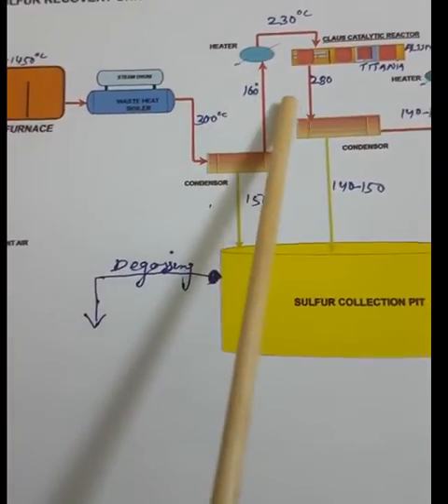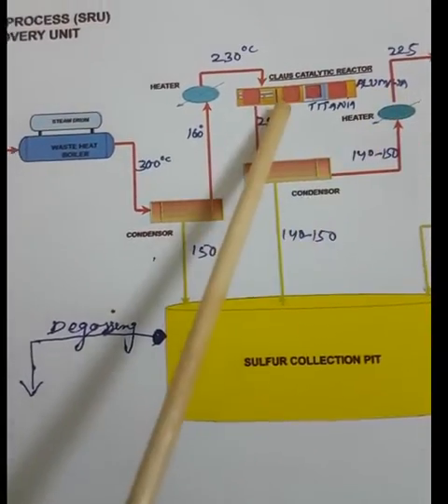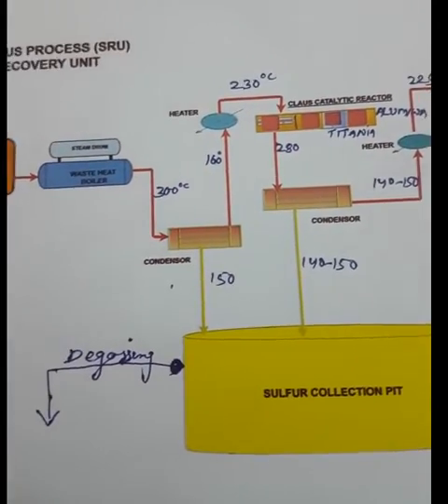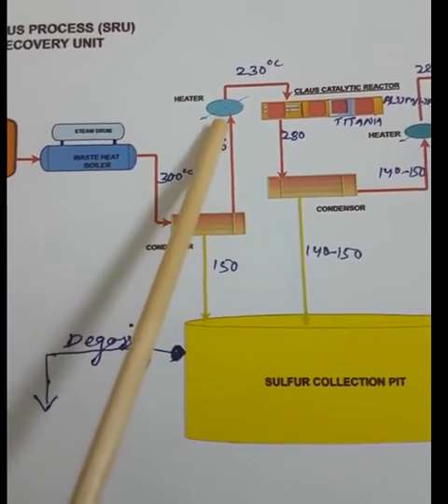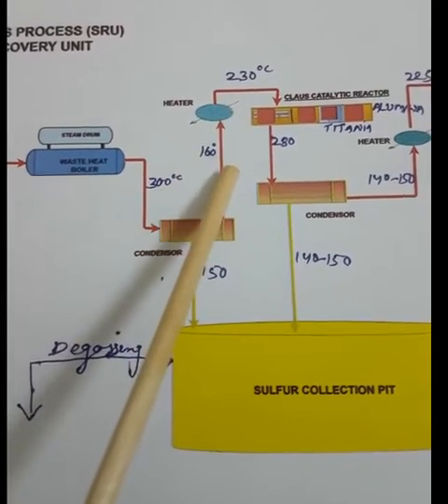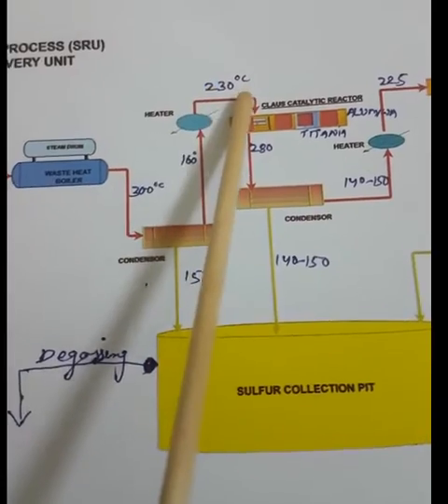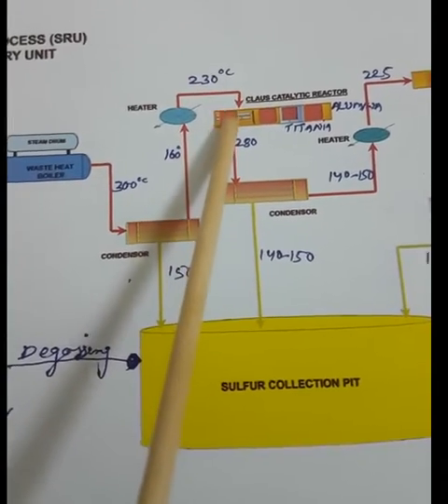In the Claus reactor, the catalyst is alumina and titania. If we send the gas at 160°C directly, there would be sulfur plugging of the catalyst bed. So we preheat the process gas to 230°C in the preheater, where steam flows in the tube side and process gas flows in the shell side — heating it from 160°C to 230°C.